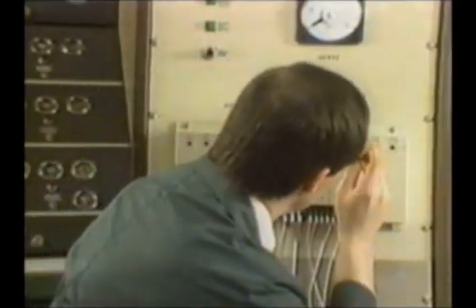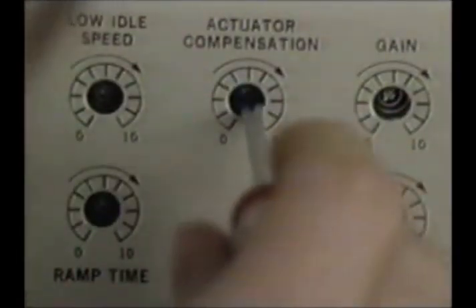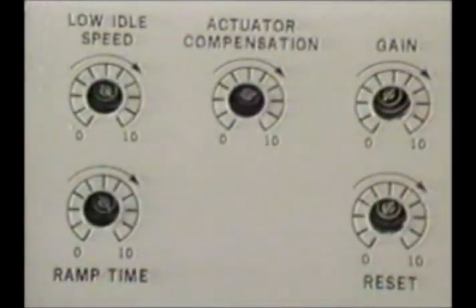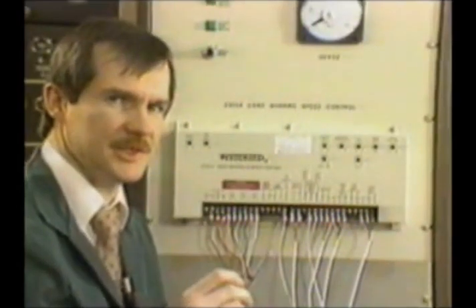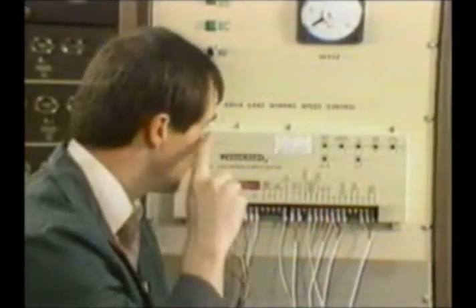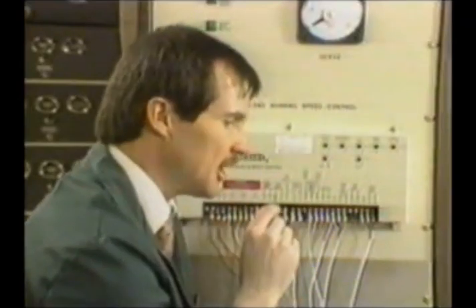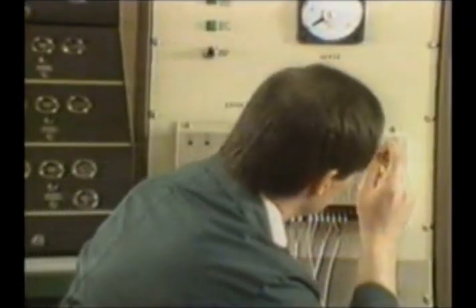So we're using a diesel engine. I'm going to set this up for 2 on the dial. You should not have to adjust that actuator compensation again once it's preset for your prime mover. The gain potentiometer, I'm going to set it mid-range. And the reset potentiometer, I'm going to set at mid-range.